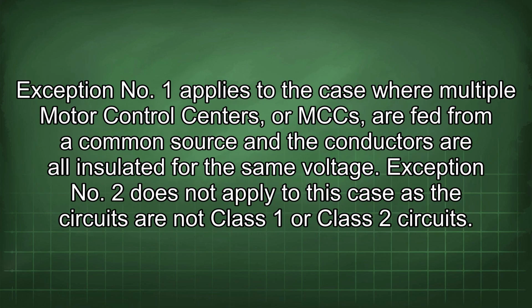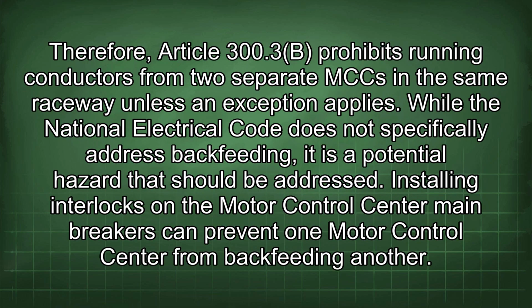Exception No. 1 applies to the case where multiple motor control centers, or MCCs, are fed from a common source and the conductors are all insulated for the same voltage. Exception No. 2 does not apply to this case, as the circuits are not Class 1 or Class 2 circuits. Therefore, Article 300.3(b) prohibits running conductors from two separate MCCs in the same raceway unless an exception applies.